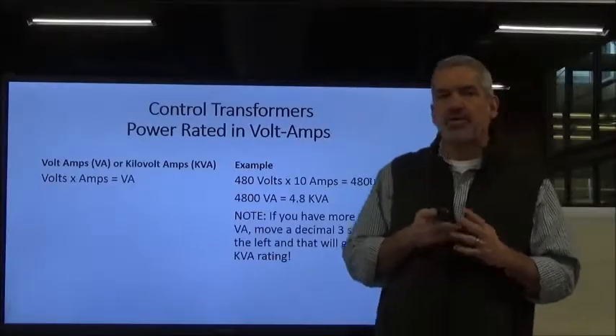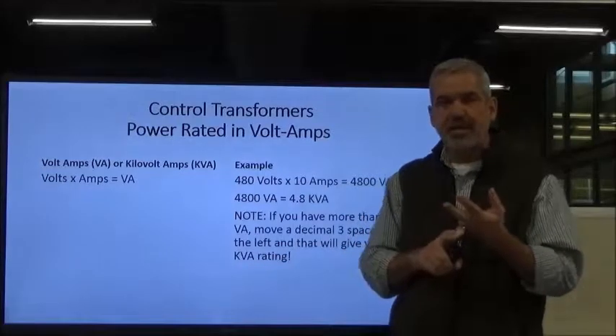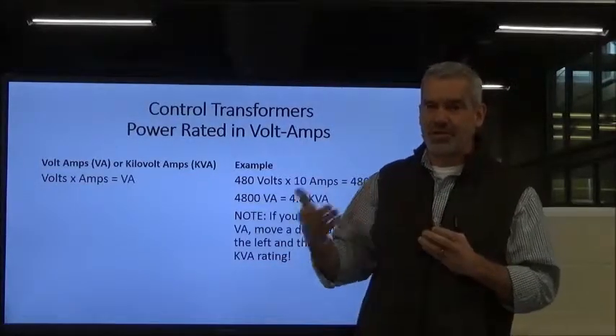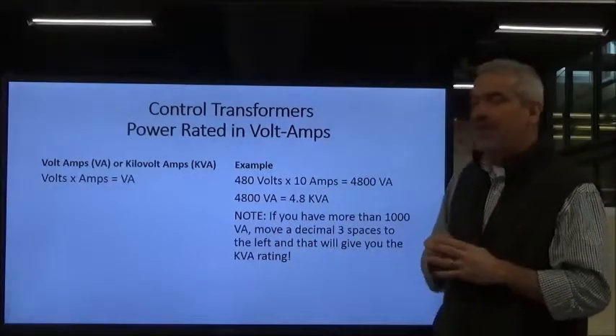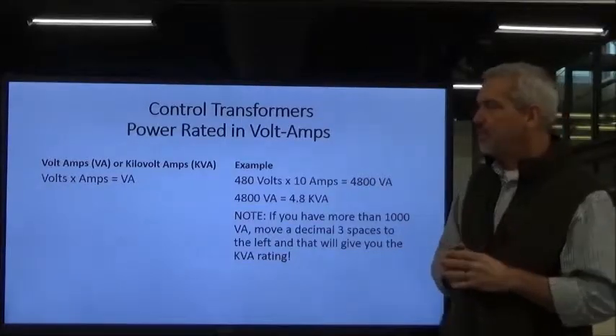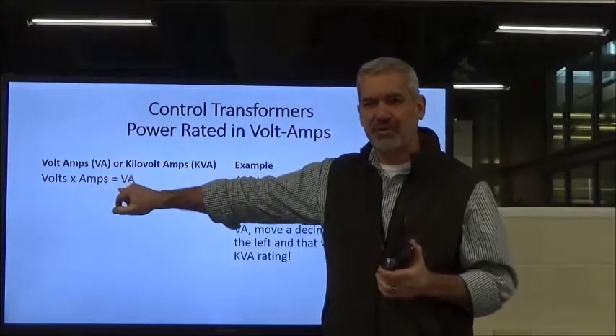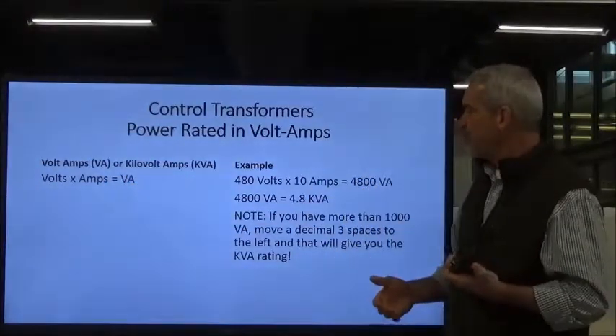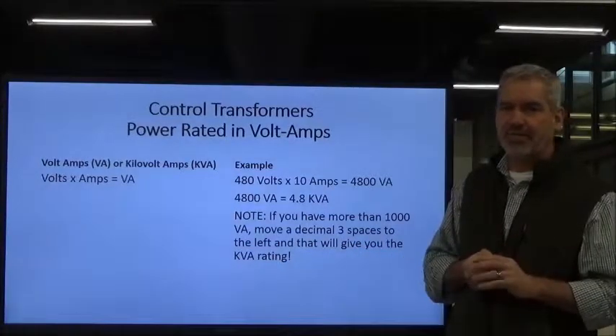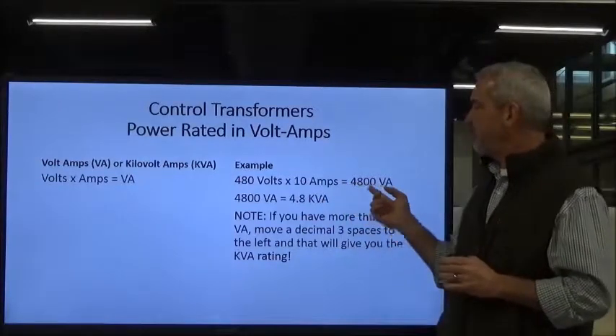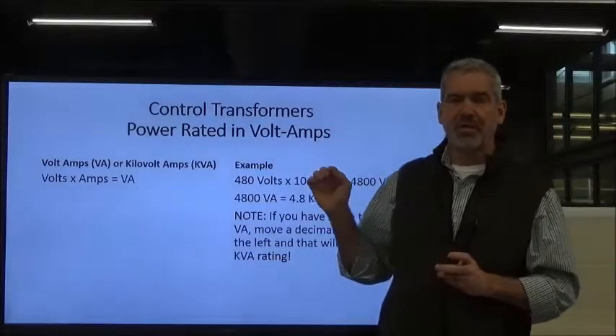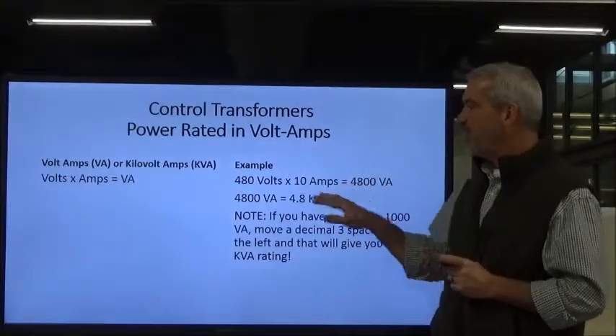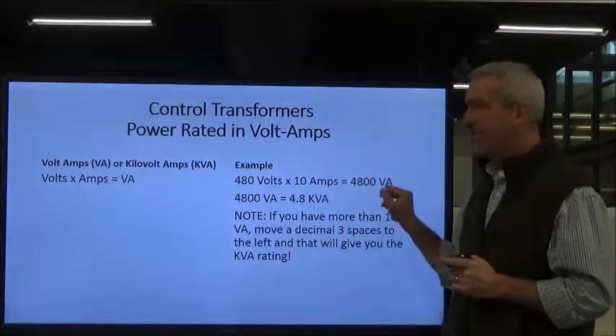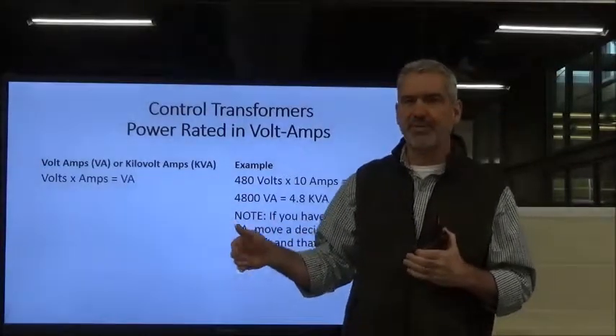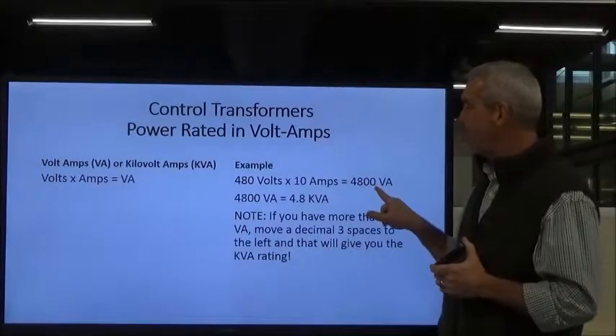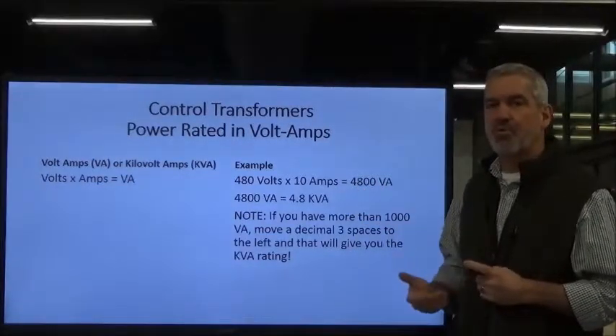All right, now transformers are rated in two different ways: kilovolt amps or volt amps. They're basically the same. It's just that one is to the thousandths and the other is not. We can figure out the volt amps on a transformer simply by multiplying the volts times the amps. For example, if our primary is going to run on 480 volts and we have 10 amps, we're going to need a 4800 volt amp transformer. There's a little bit more to calculating the sizing of transformers than that, but in general terms, volts times amps gives us 4800 volt amps. I said it was also rated in kilovolt amps. All we've got to do is move our decimal place 3 times to the left, 1, 2, 3, right between the 4 and the 8, and it becomes 4.8 kilovolt amps.